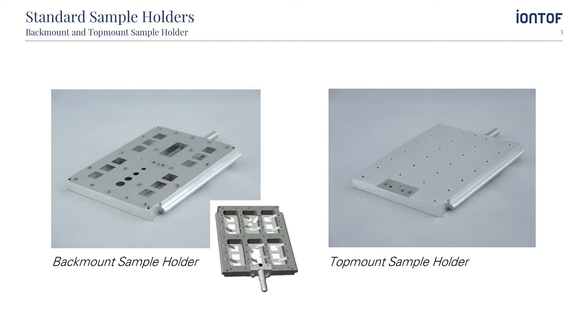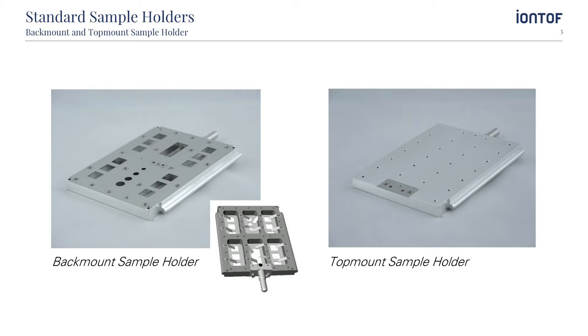There are two standard sample holders used in our ToF-SIMS machines. The backmount holder retains all the samples behind a mask at the same height. The samples are held in place by means of spacer blocks and springs. The spacer blocks enable samples of varying thickness to be mounted in the holder.